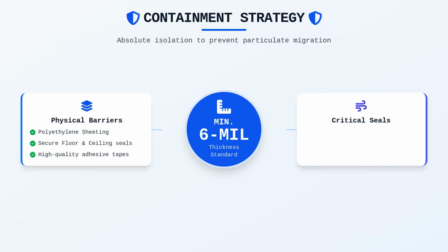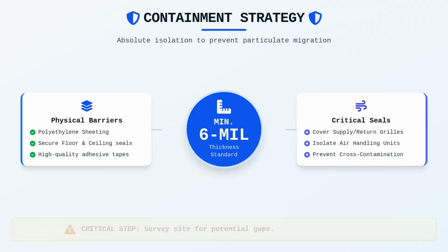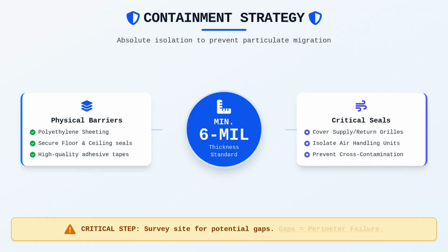Beyond simple barriers, we must address critical seals on supply and return registers or grills by covering them with plastic and sealing the perimeter edges completely. This ensures that the air handling unit remains isolated from the specific zone under maintenance, preventing cross-contamination while the system is inactive. You should always survey the site for potential gaps where air could bypass these seals, as these represent points of failure in your containment perimeter.